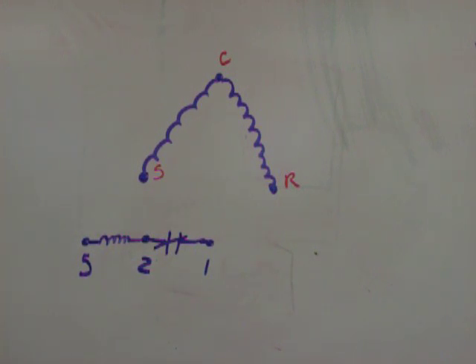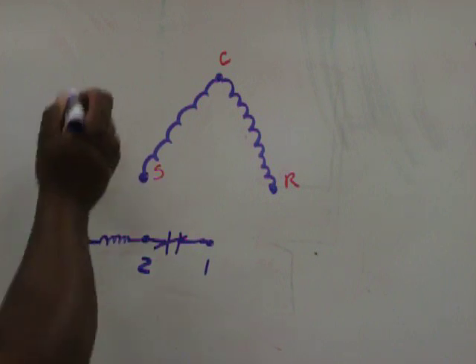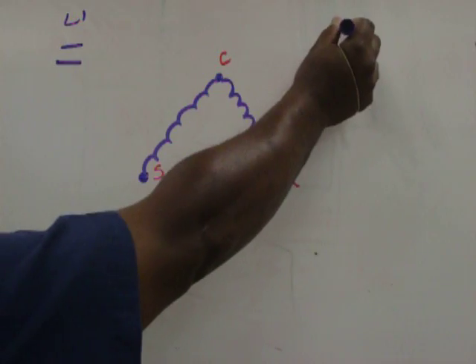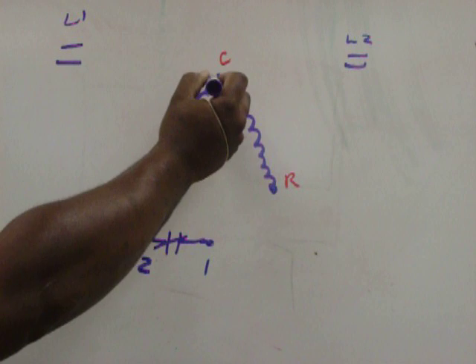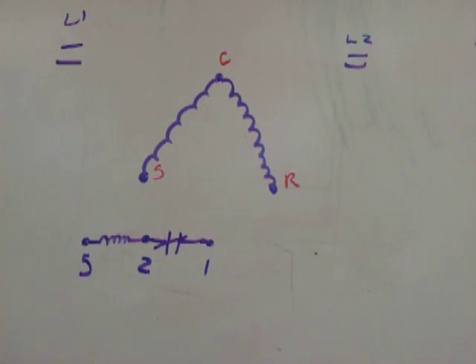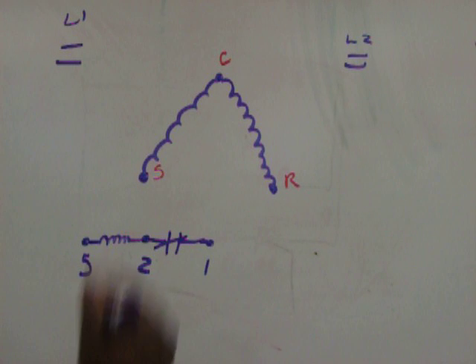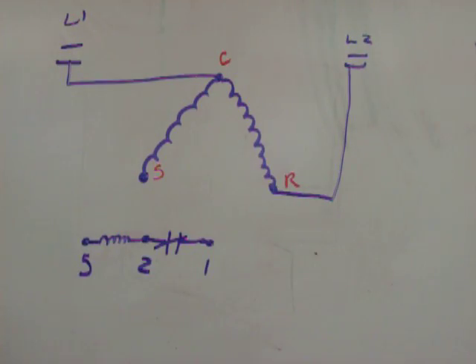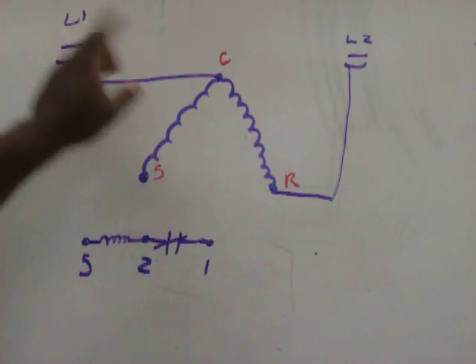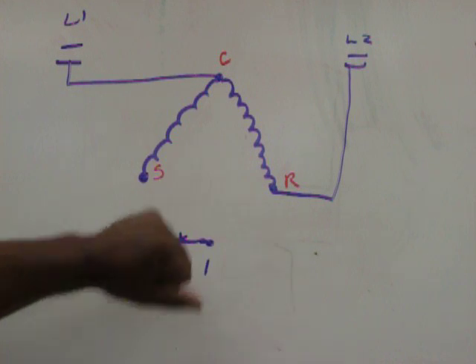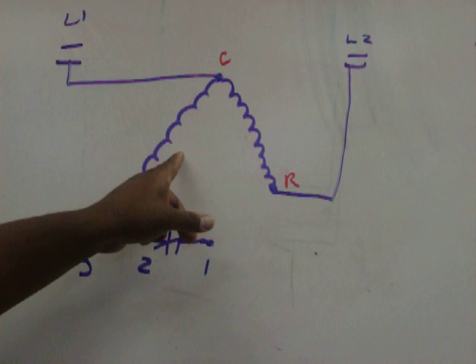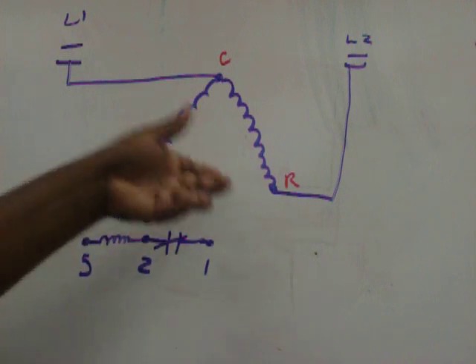Now, how is that wired up? Let's draw a contactor in here. Here's one side of power as your other side of power. We just call it L1, L2. And again, you need to go back to the other video to learn about motors. Common goes to L1. Run goes to L2. So if we closed L1 and L2, it would be energizing run winding only. But that wouldn't be enough start torque to get this compressor running.